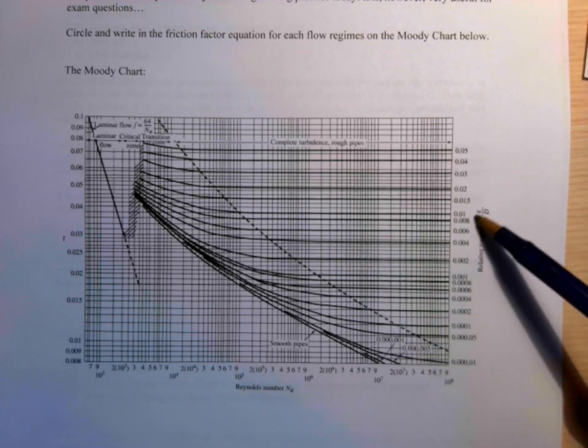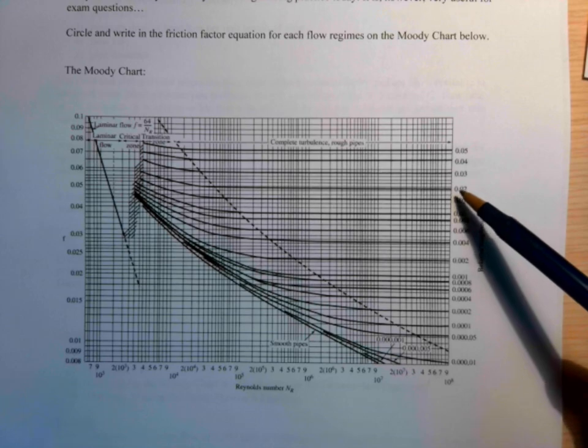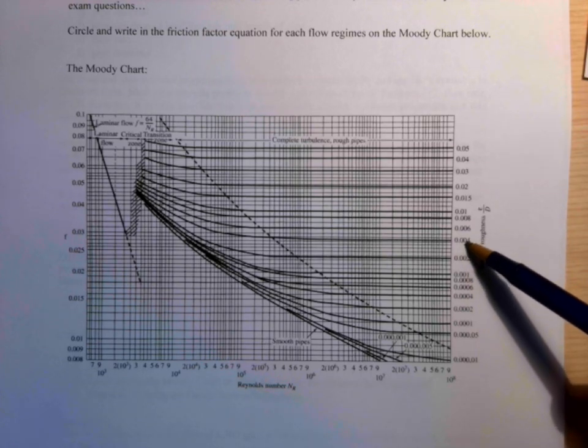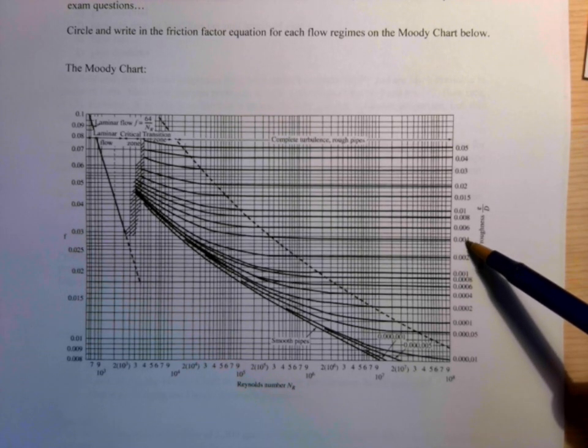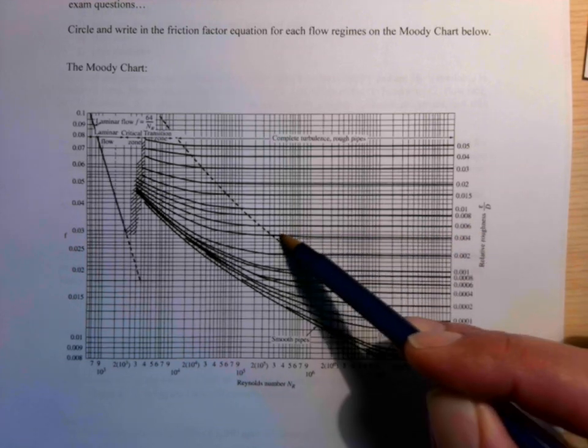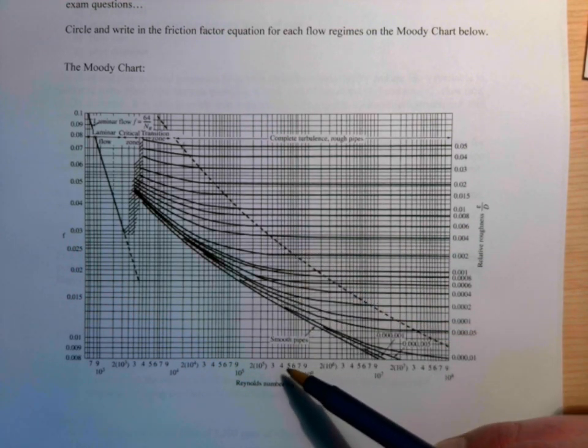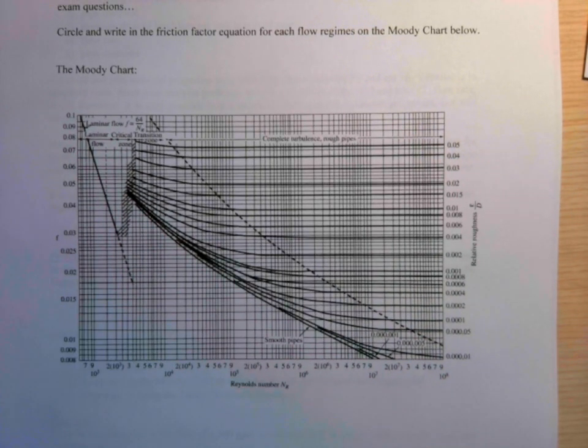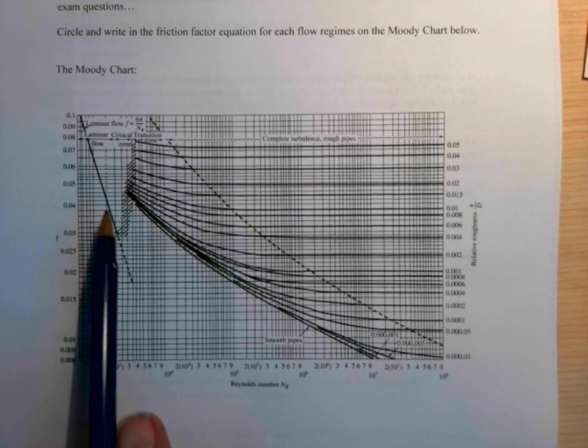We find the relative roughness, nondimensional number here, one of these dark lines. We may have to draw one in if we're in between, like between these two would be 0.05. Then we follow that over to where we're at the Reynolds number here on the x-axis, and then we read the friction factor from the left side. So that's how we use this.